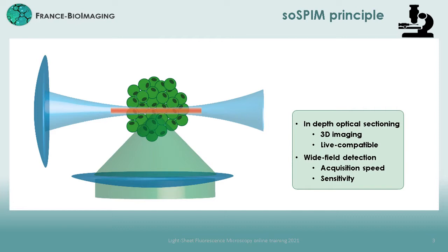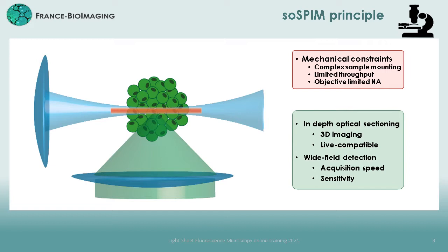Standard light sheet implementations are based on at least two objectives perpendicular to one another, in order to create a thin light sheet on one side and collect perpendicularly the fluorescent signal on the other side. This specific illumination architecture allows for unprecedented capacity to image living samples in 3D at high spatial and temporal resolution and with very low photodamaging effects.